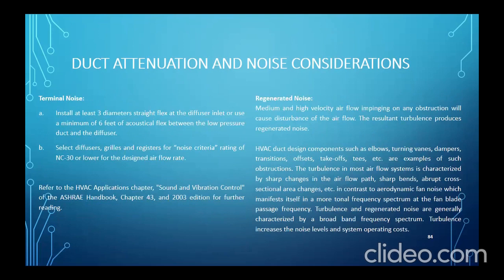So, terminal noise. A. Install at least 3 diameters straight flex at the diffuser inlet or use a minimum of 6 feet of acoustical flex between the low pressure duct and the diffuser. B. Select diffuser grills and registers for noise criteria rating of NC30 or lower for the design airflow rates. So, sa air conditioning natin, meron tong selection sa air distribution. Okay? So, also refer to the ASHRAE Applications chapter, Sound and Vibration Control, in the handbook, chapter 43, 2003 edition for further reading, or plus 2006, 2009. Check nyo kung equal siya. Okay?